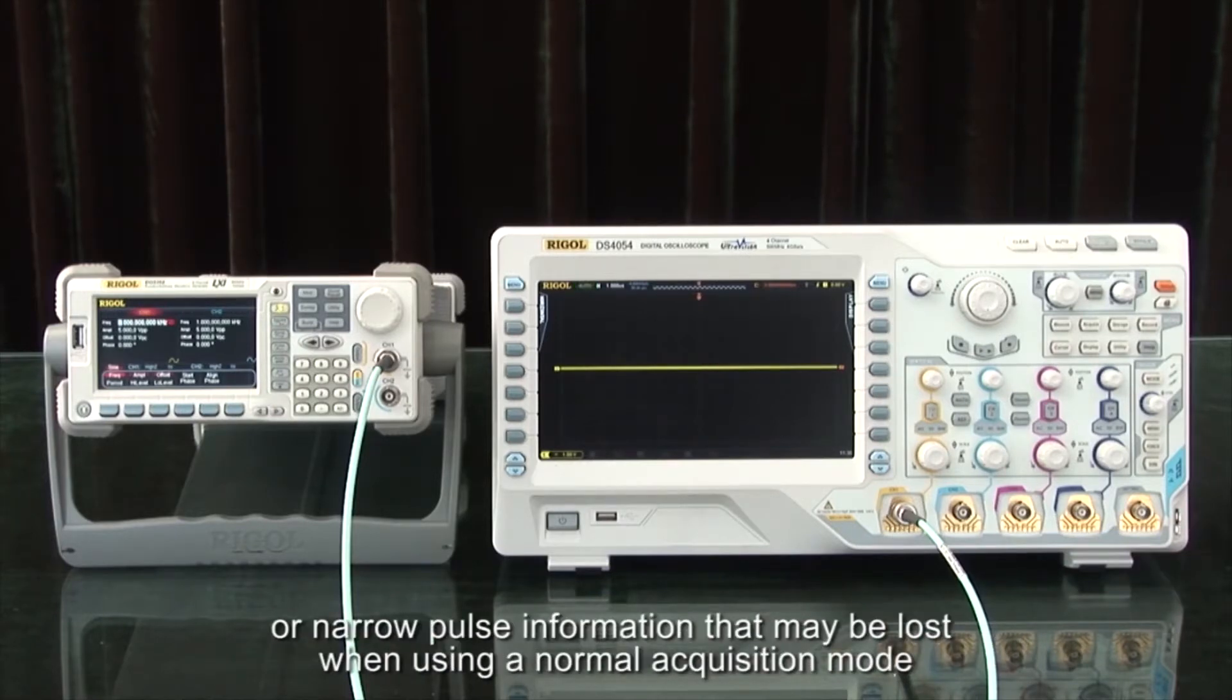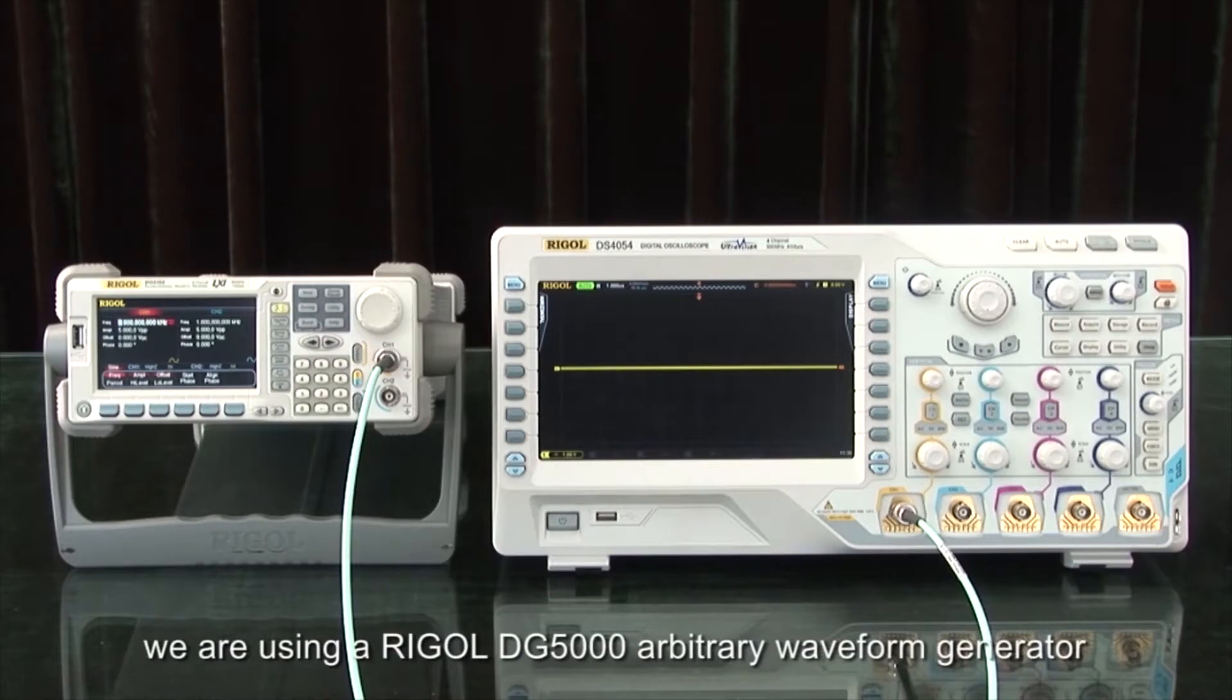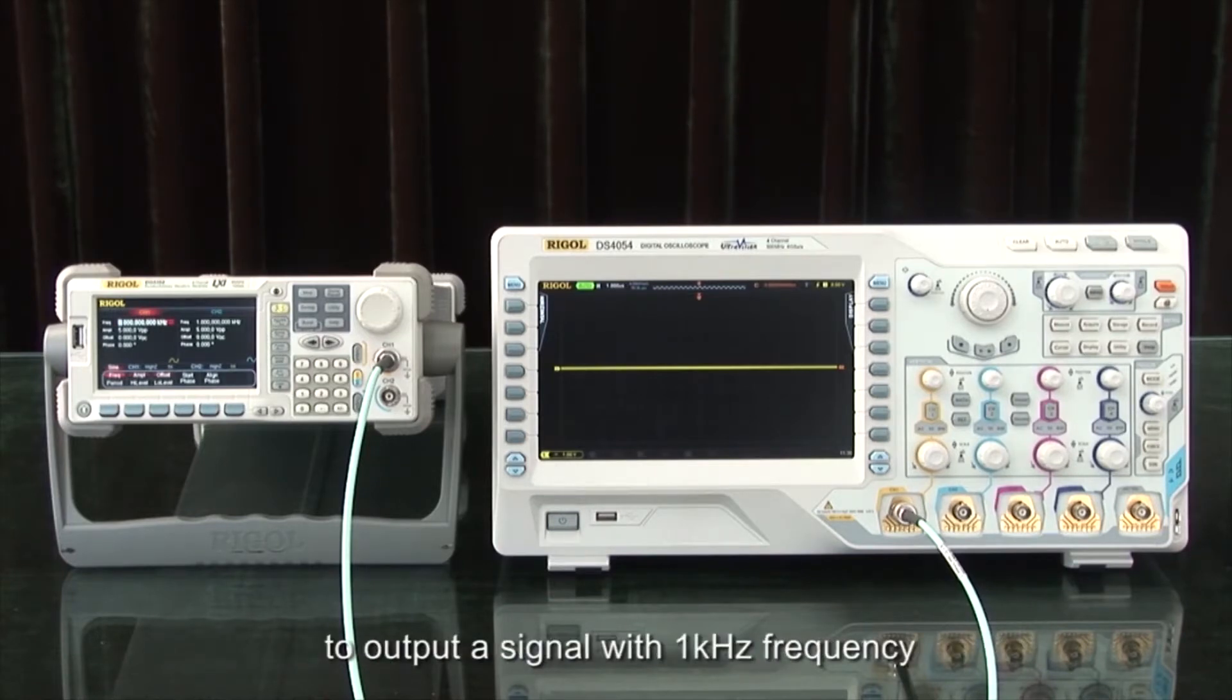Let's compare normal mode and peak detect mode. In this example, we are using a Rigol DG5000 arbitrary waveform generator to output a signal with 1 kilohertz frequency, 5 volt peak-to-peak amplitude, and a 10 nanosecond pulse width.